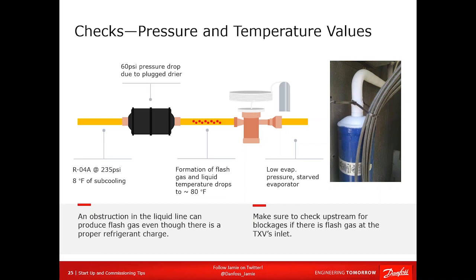So if you've even got an 8 or 10 degree temperature difference across your dryer, that's a problem because it's sized for about half a degree. So that means it's plugged. So eliminate any upstream issues before you have that metering device pulled.